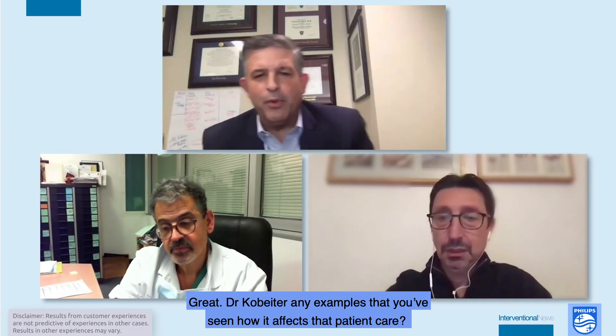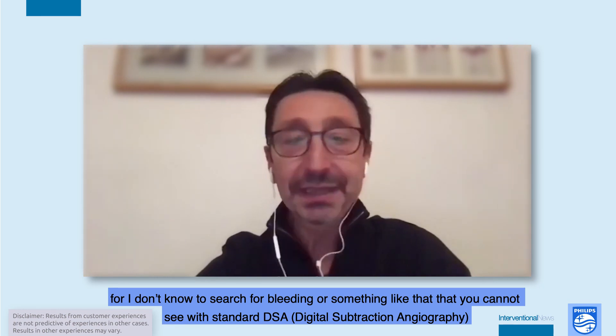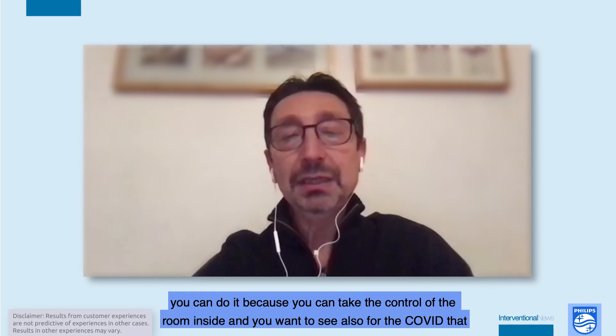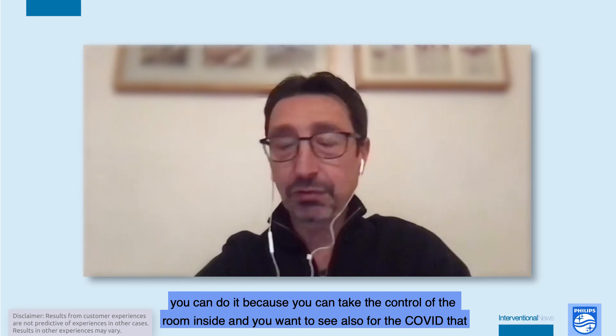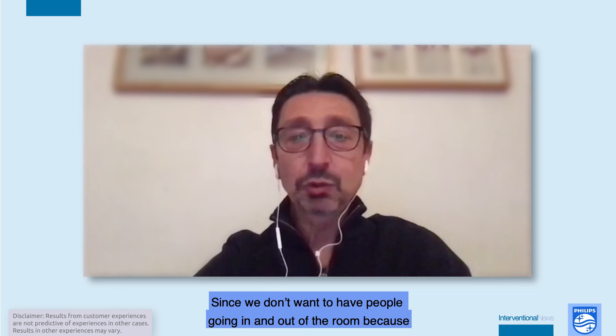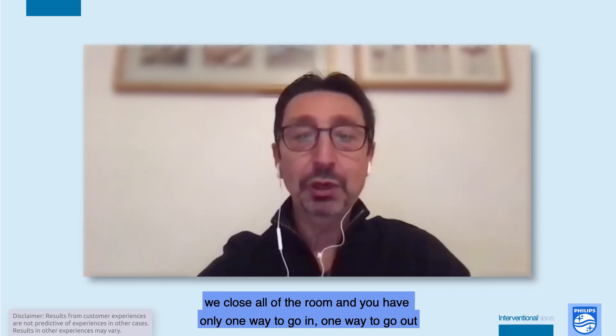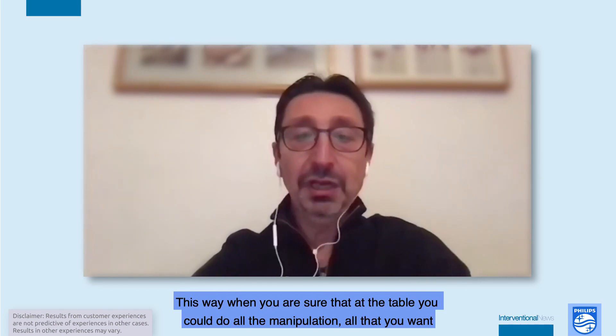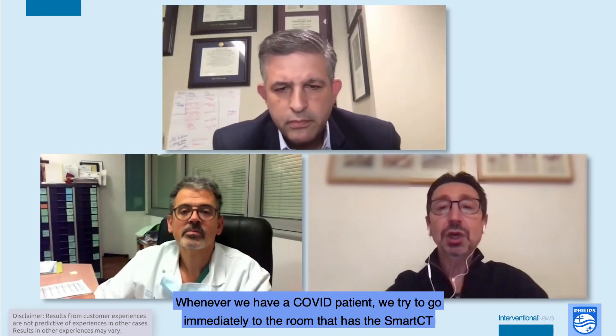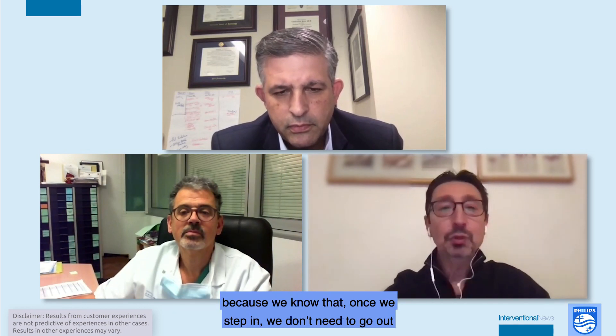Dr. Kobeiter, any examples of how Smart CT affects patient care? If you don't have skilled techs at 2 o'clock in the morning and still need to do a CBCT — for example, to search for bleeding not visible on standard DSA — you can do it because you control the room from inside. Also during COVID, since we don't want people going in and out of the room, whoever has a COVID patient goes immediately to the room with Smart CT, because once you step in, you don't need to go out.